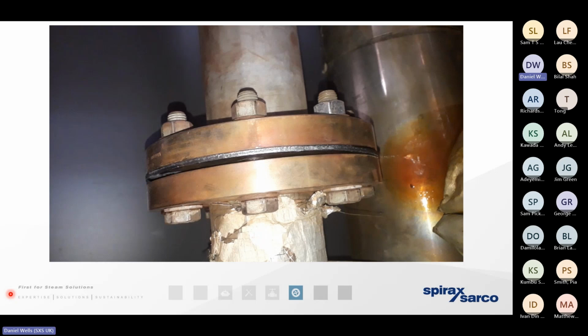It could be down to the fact that the boiler is producing steam that is very, very wet, and therefore it's condensing out in the pipework. Therefore, we've got a very large condensate load. The steam traps could be undersized. The steam traps could have failed in the closed position. We could have damaged insulation, which means we've got more heat loss than we're expecting. We could have undersized pipework, which means the condensate and the steam are moving at too great a velocity.